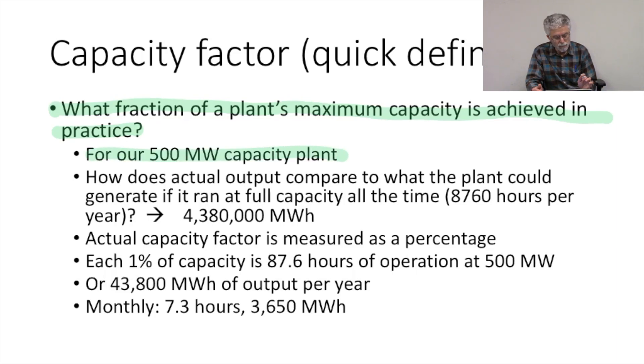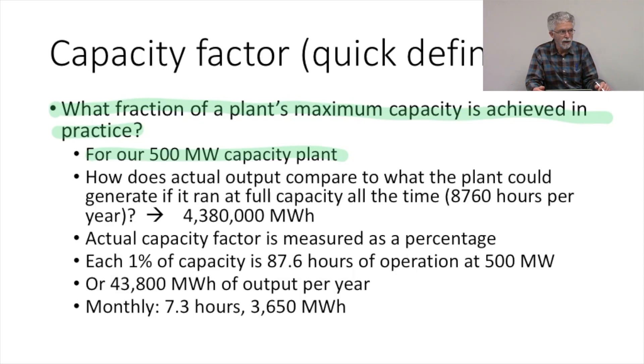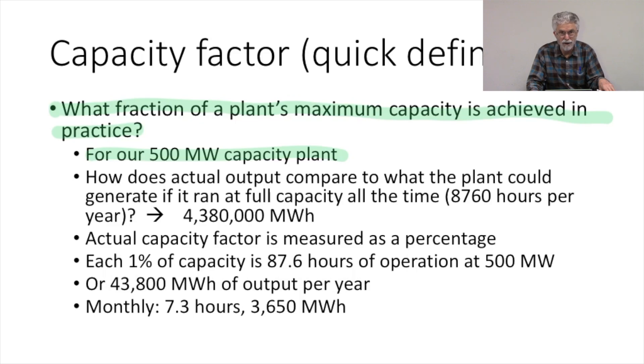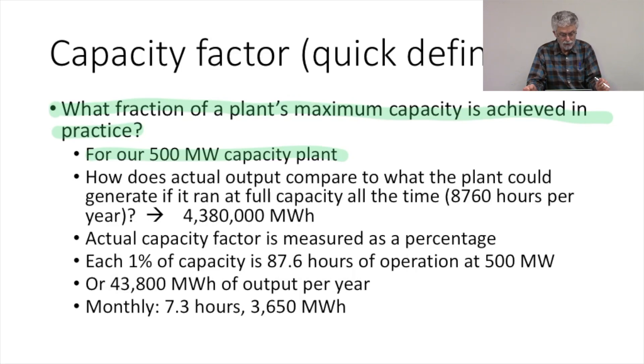Let's go back to our 500 megawatt power plant. How does the actual output compare to what the plant could generate if it were running at full capacity all the time? A year is 8,760 hours, so the maximum output you could conceivably get is if it were running at the full 500 megawatts for the full 8,760 hours a year — that would be 4,380,000 megawatt hours in the year. That would be the full capacity of the power plant.